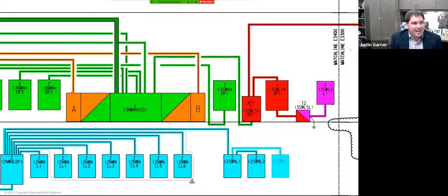You notice you have an A and a B side. So we actually have redundant feeds there. There is a tie here in the middle that is normally open, but if one of these were to be lost, that tie could be closed and this entire gear could be fed from one side or the other. That's very common in commercial facilities these days. Usually doesn't affect things that we do on the TAB side very often, but it is nice to know what kind of sources you have and things like that.